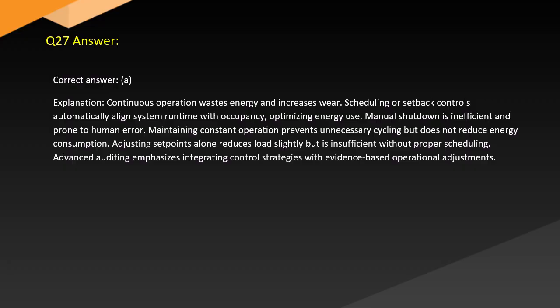Answer. Correct answer. A. Explanation. Continuous operation wastes energy and increases wear. Scheduling or setback controls automatically align system runtime with occupancy, optimizing energy use. Manual shutdown is inefficient and prone to human error. Maintaining constant operation prevents unnecessary cycling but does not reduce energy consumption. Adjusting set points alone reduces load slightly but is insufficient without proper scheduling. Auditing emphasizes integrating control strategies with evidence-based operational adjustments.